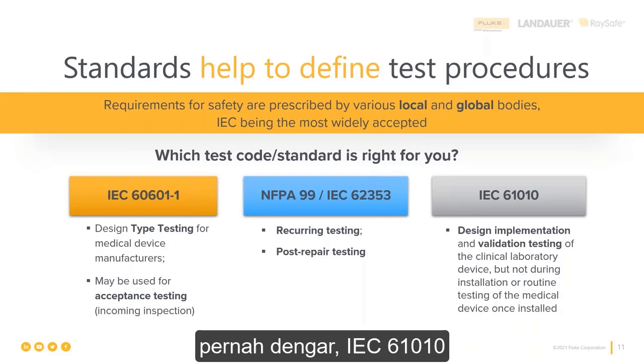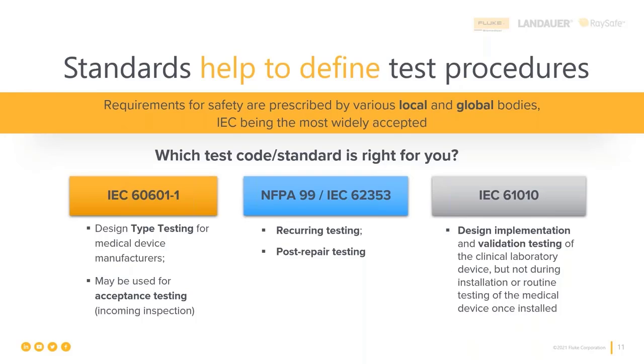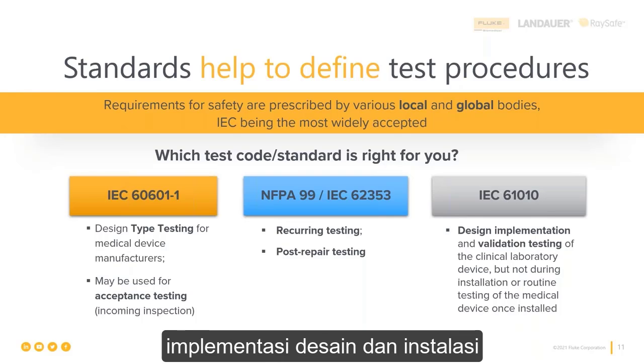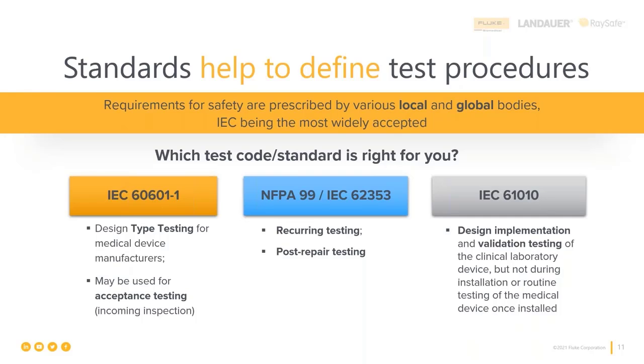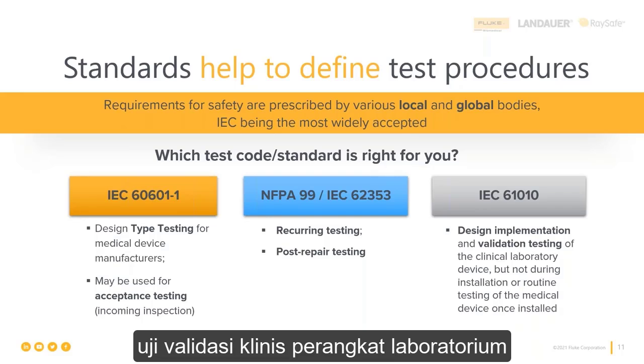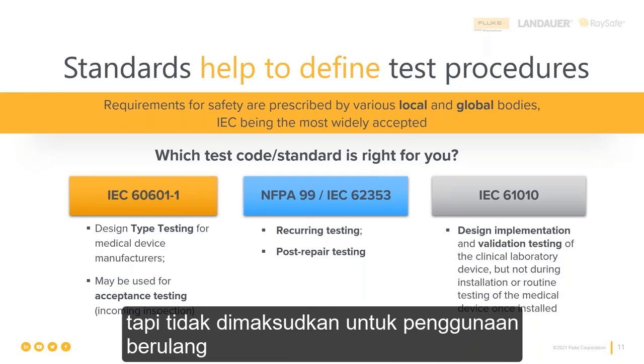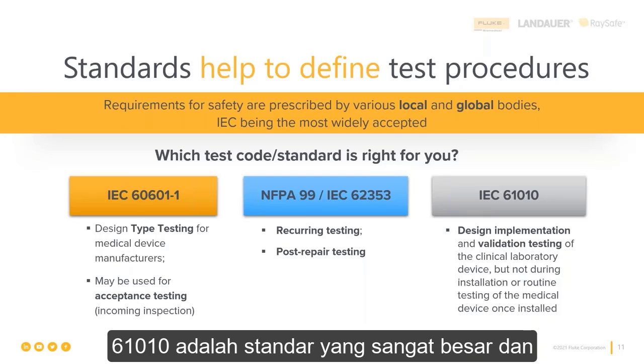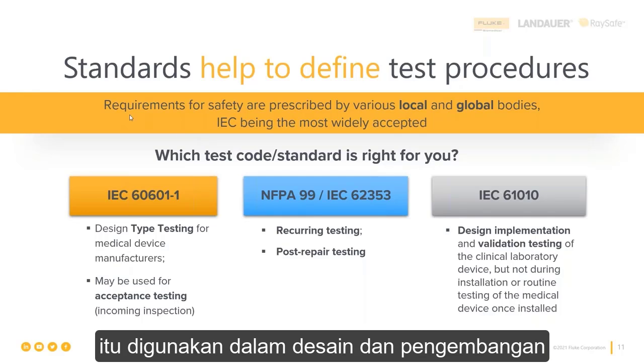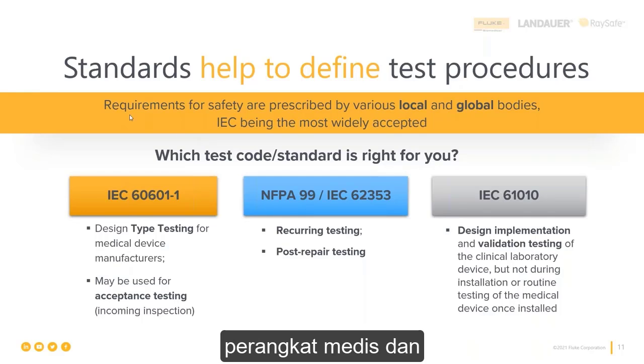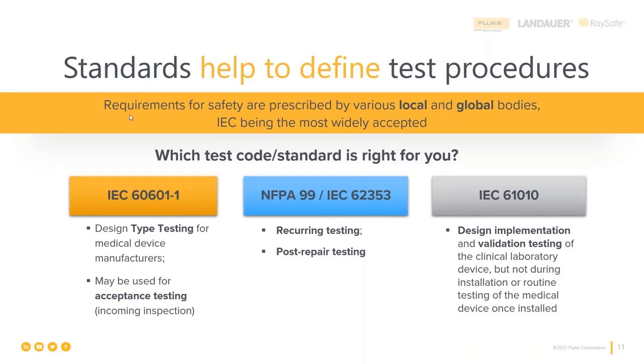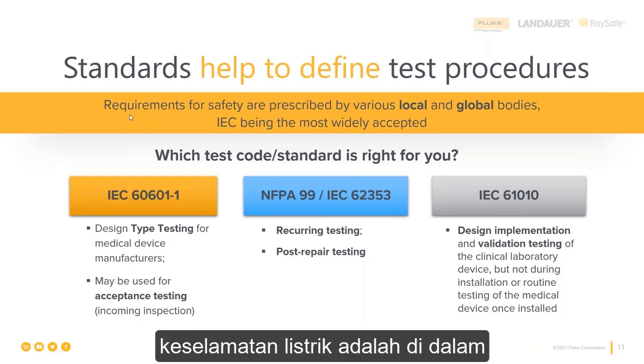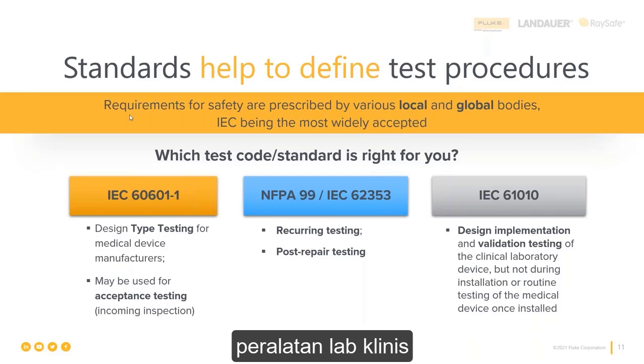There's another standard that you may have heard of, the IEC 61010, and this is used for design, implementation, and installation validation testing of clinical laboratory devices, but not intended for repeated use. The 61010 is a very big standard, and it is used in the design and development of medical devices and our test instruments, but typically where we worry about it for electrical safety is in clinical lab equipment.